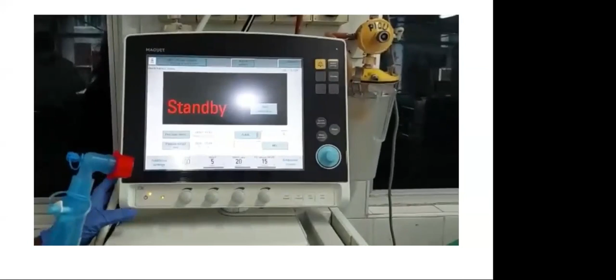So once we do that, we have to select which mode, adult mode or infant mode. As I said, infant mode is mainly suitable between 0.5 to 30 kilos and adult mode between 10 to 250 kilos. But the minimal tidal volume in the adult mode is only 100 ml. So if it's an infant, better to use infant mode. So you have to press there.